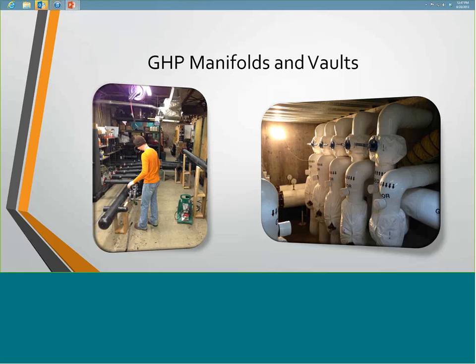The manifolds use a lot more different parts and pieces. Out in the field, it's almost all high-density polyethylene piping, bentonite drilling fluids and grouts, and silica sand for enhancement of the bentonite. But when you start getting into actual mechanical interfacing into the building, you start seeing valves, balancing valves, ports, pressure gauges, temperature gauges, fittings, flanges, and bolts. There's a larger variety of parts and pieces that go into the manifolding.